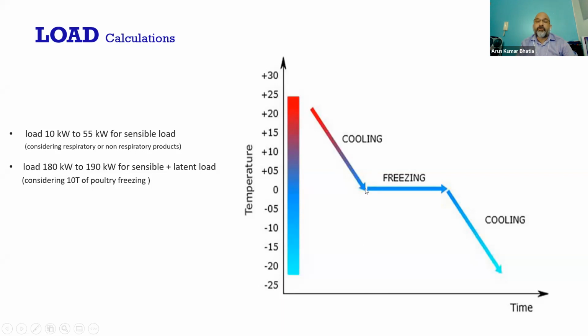But when we want to freeze this product, the curve becomes flat. The temperature is not reducing. The compressor or refrigeration device keeps working continuously from this point of time to this point of time, consuming a lot of energy. This energy is used to freeze, because the latent heat of freezing requires a lot of time and a lot of calories.